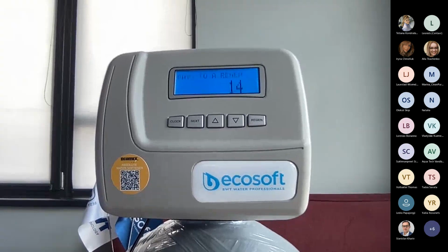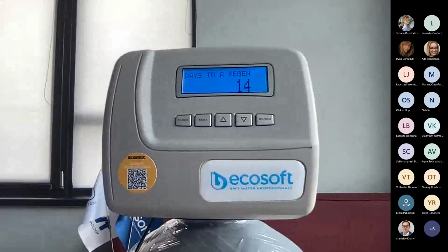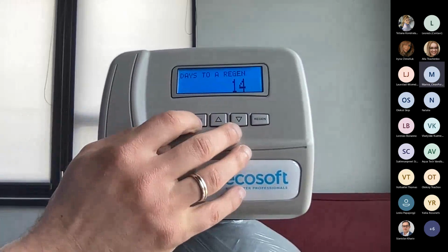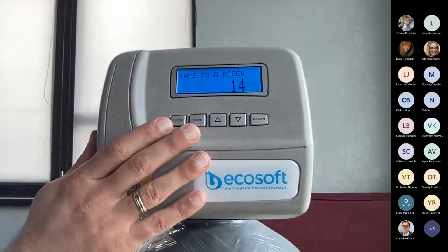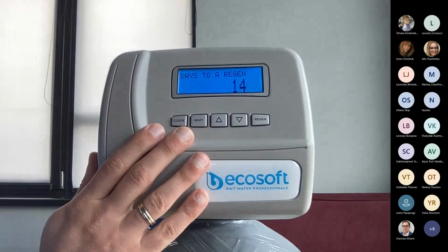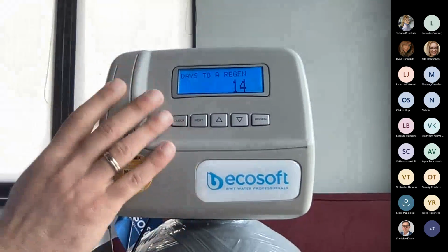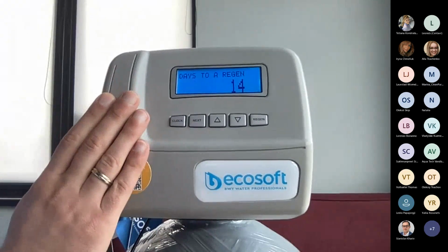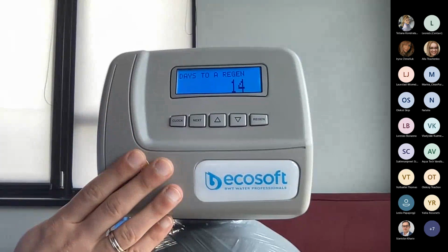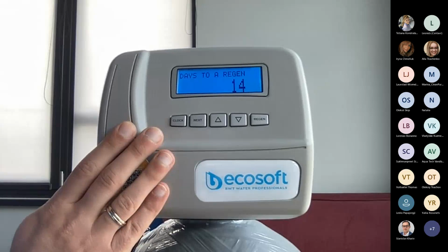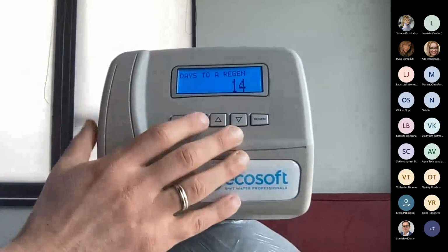So there were no replies to my question on how many days or how many hours the valve would keep the time. So the answer is, if the valve was in operation for 24 hours, then the batteries and the condensers are charged, and when there is an electricity shutdown, even after 72 hours of no electrical supply, the valve would keep the time. So you would not have to reset the time again.